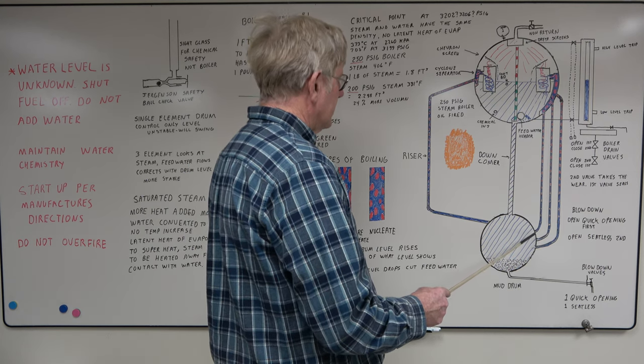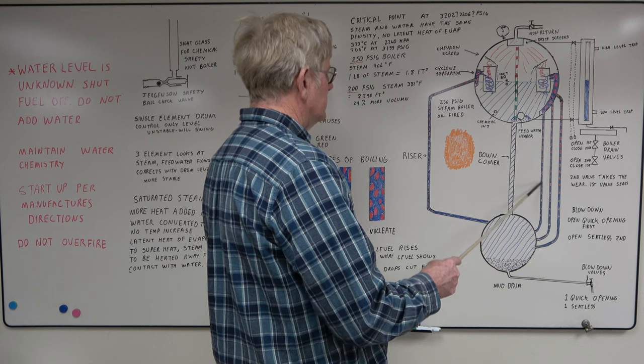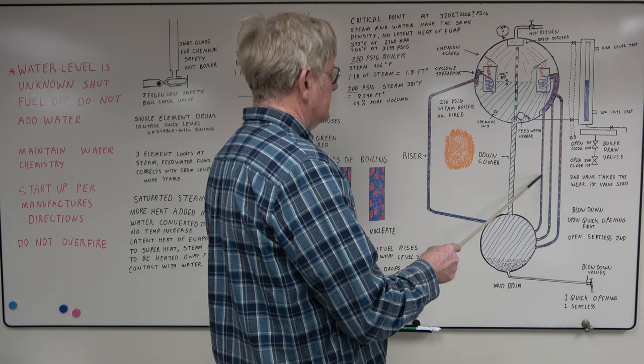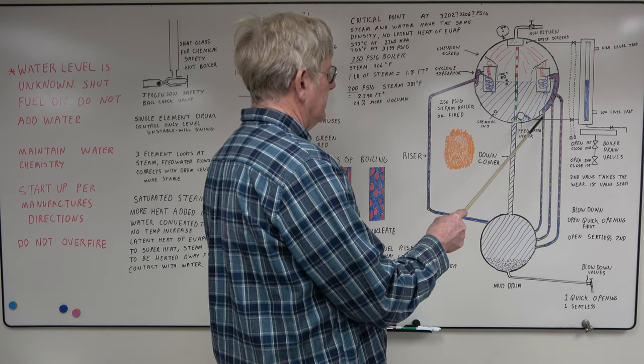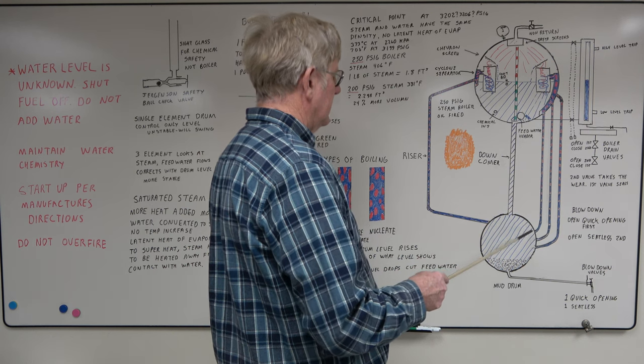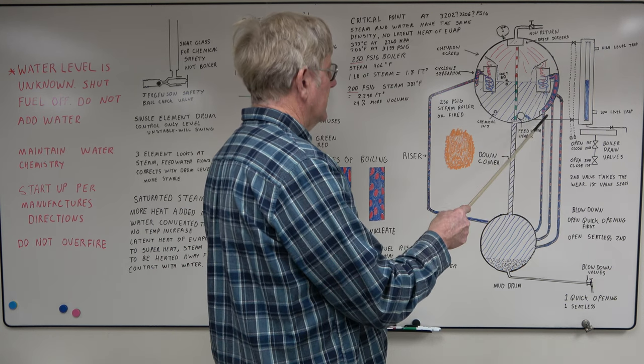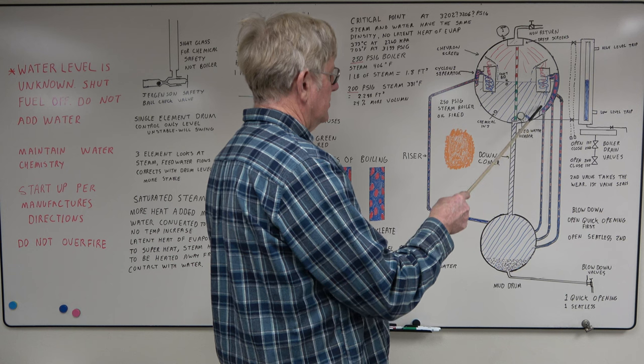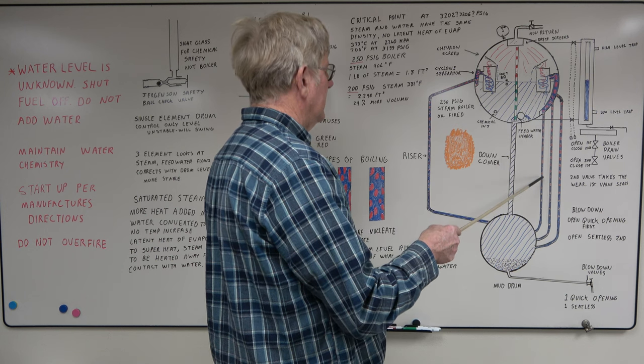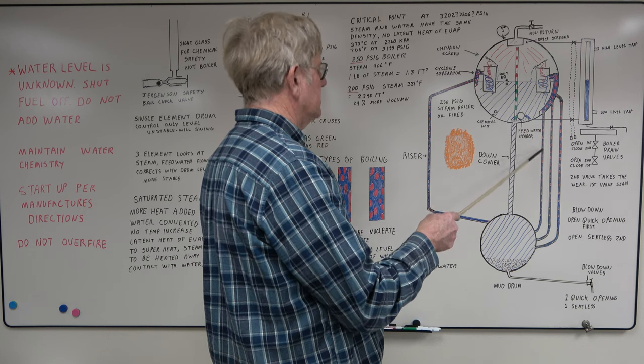The way this works, as your water is heated, it starts forming steam bubbles. So it gets lighter. You have a steam water mix which is a lot lighter than the water in the downcomer, so it creates a circulation. The length of tube here is important too to increase circulation. And at higher loads, you have more steam bubbles in the mix and it flows quicker.